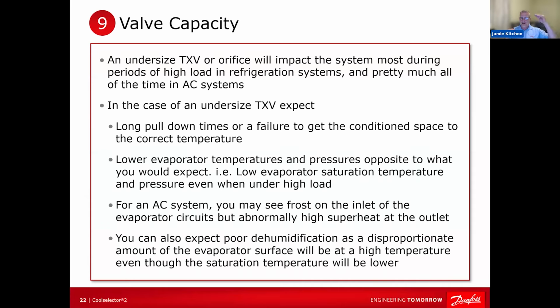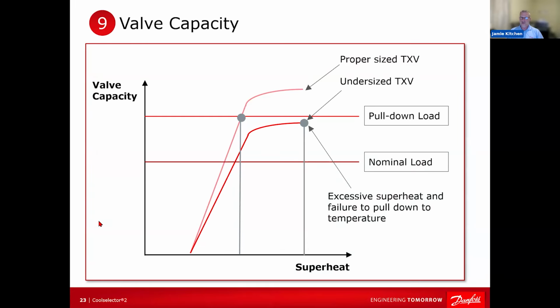Now, if your evaporator's too big, will it still work? Sure. But it's not going to work at the conditions you want, and you're not going to get the dehumidification or lack of dehumidification that you want, right? The worst thing with TXVs is undersized. If they're oversized, even 20, 30%, it ain't going to matter. They're going to throttle down no matter what anyways. They'll throttle down to 50, 40% capacity, right? No problem. As long as they're installed correctly and all the other stuff we talked about.